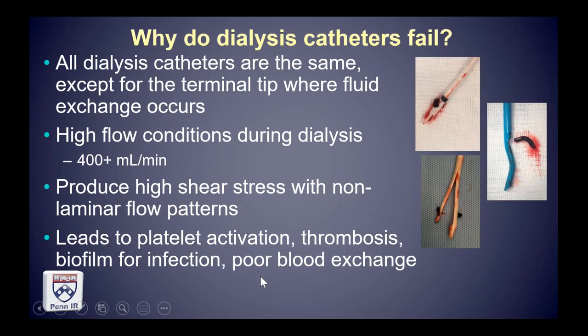Dialysis catheters are all the same except for the tip, and the tip is where fluid exchange occurs. During hemodialysis use there are high flow conditions — 400 milliliters per minute is typical. When you exchange blood through a catheter at flow rates vastly higher than a typical IV line or PICC line, it produces immense near-wall shear stress factors with non-laminar flow patterns.